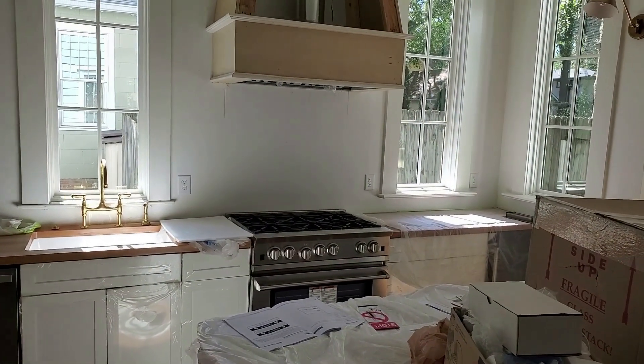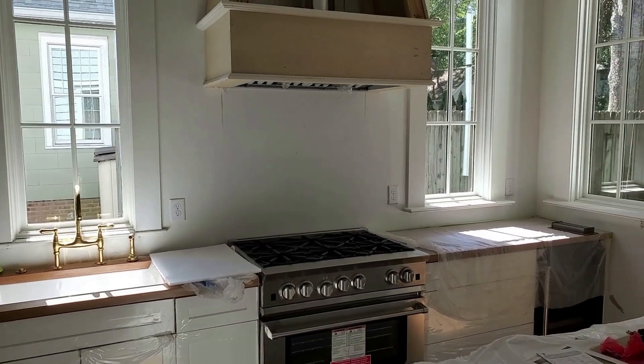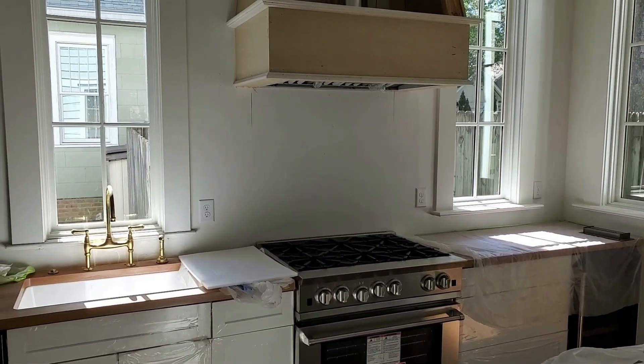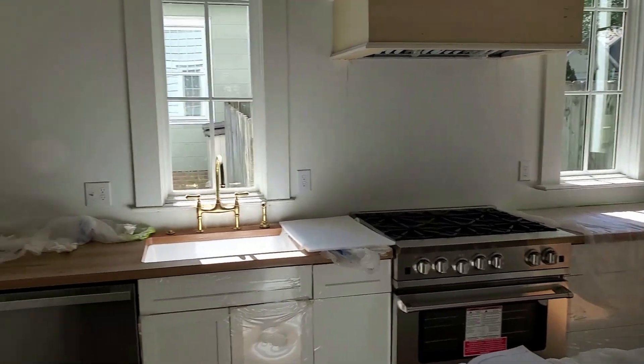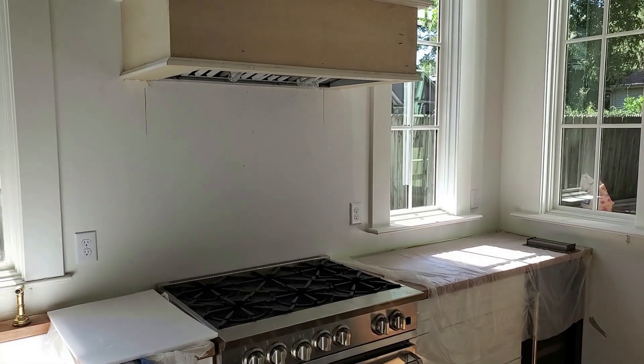We're back with some more code violations. What you are looking at is a kitchen — a newer kitchen exhaust hood right up under a new gas stove. This is for my mechanical contractors. This particular kitchen exhaust hood is rated at about 590 CFM. Code says anything over 400 CFM requires makeup air, so you have to bring in as much as you exhaust. Think about that when you're installing these huge commercial-sized kitchen exhaust hoods. Definitely talk it over with the builder or the homeowner. They're renovating the kitchen, but you have to factor in the CFM — anything over 400 CFM, you have to bring in makeup air, as much as you exhaust.